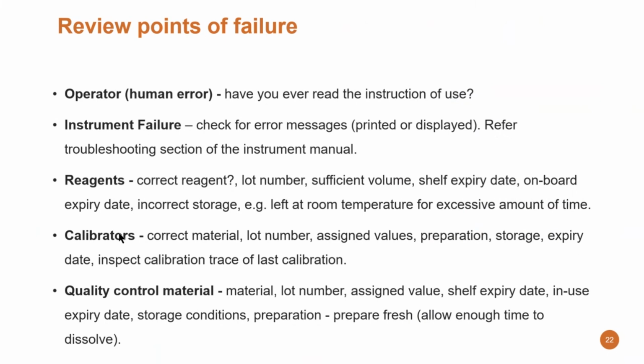The calibrators: have you used the correct calibrator, which is recommended by the manufacturer of the reagent and instrument? Check the lot number, the assigned values, the preparation, the storage conditions, and also the expiry date. Inspect the calibration trace of the last calibration. Quality control material: have you used the correct material, the right lot number? Check the assigned value, the expiry date, and in-use expiry date. Storage condition as well. Preparation: prepare it fresh or allow enough time to dissolve, or if you take it out of the freezer or refrigerator, wait till the QC material is in the proper condition to be used on the instrument.